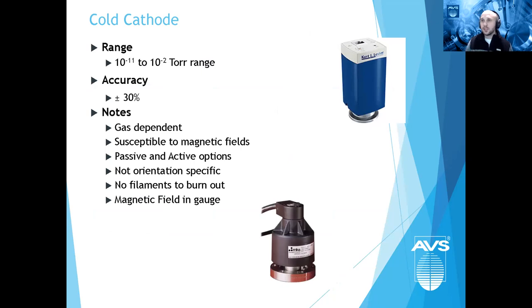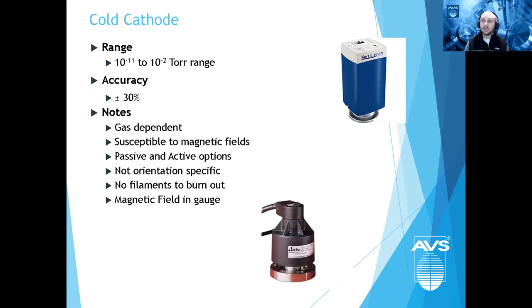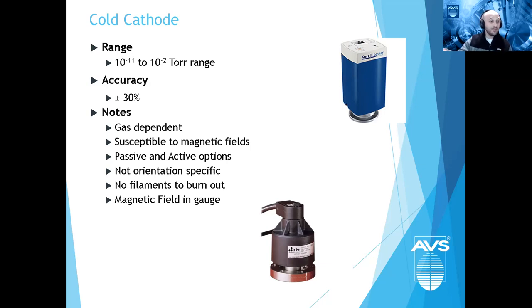Cold cathodes: 10⁻² to 10⁻¹¹. Active versions may keep you at 10⁻⁹; passive gets into the 10⁻¹¹ range. No filaments to burn out, which is a nice advantage. There are internal magnets, so if you have magnetic fields in your process, that's a consideration, though shielding these days largely handles that. Earlier cold cathodes were essentially very expensive paperclip collectors — you could literally pick up paperclips with them — but modern designs have resolved that issue.